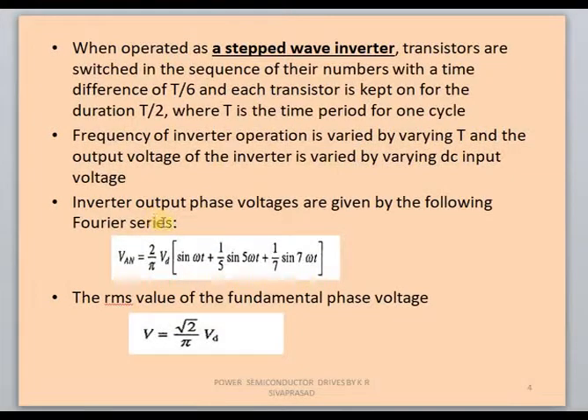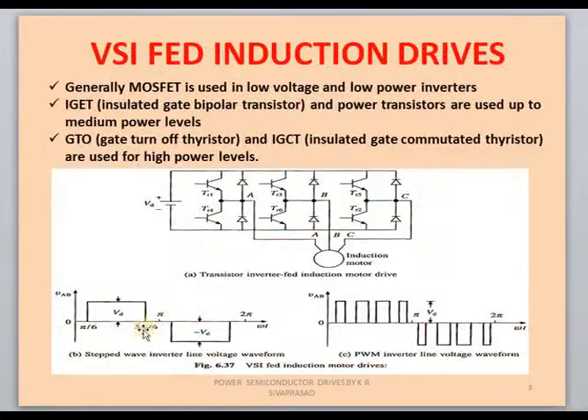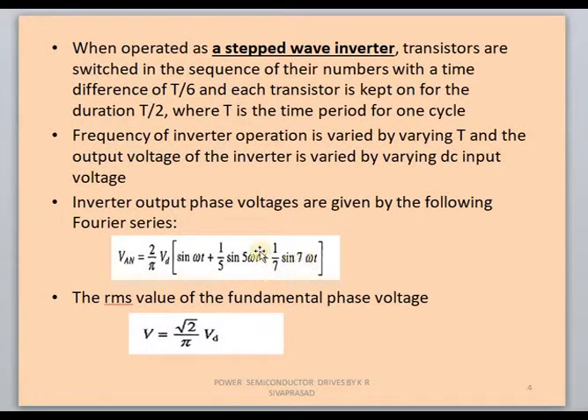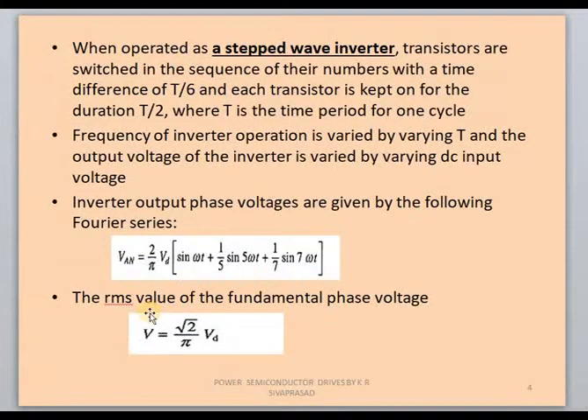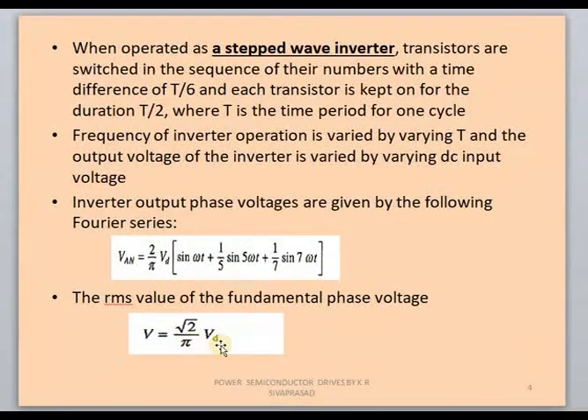The frequency of the output voltage is varied by varying the switches. The output phase voltage of the square wave inverter is: V_an = (2/π) × V_d × [sin(ωt) + sin(5ωt)/5 + sin(7ωt)/7 + ...], where the 5th and 7th are harmonic components and sin(ωt) is the fundamental component. When calculating torque generation, you consider the fundamental component. The RMS value of the fundamental phase voltage is (√2/π) × V_d, so by changing V_d we can change the voltage value.